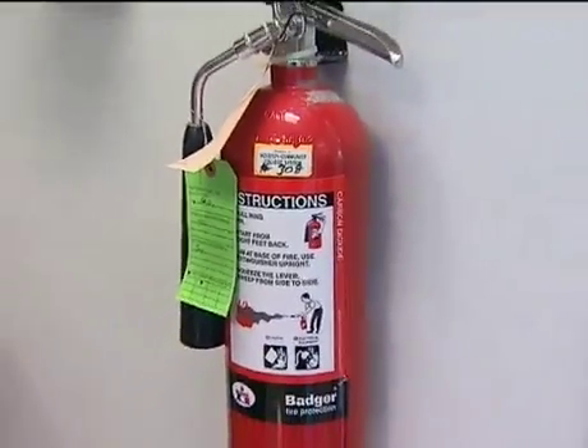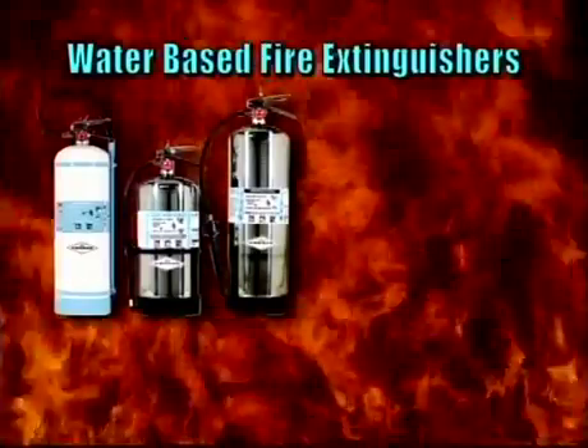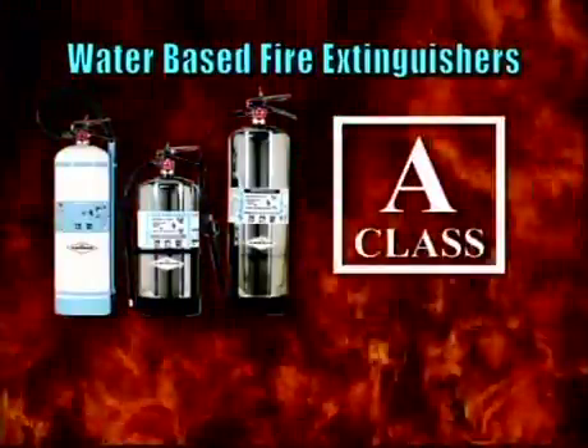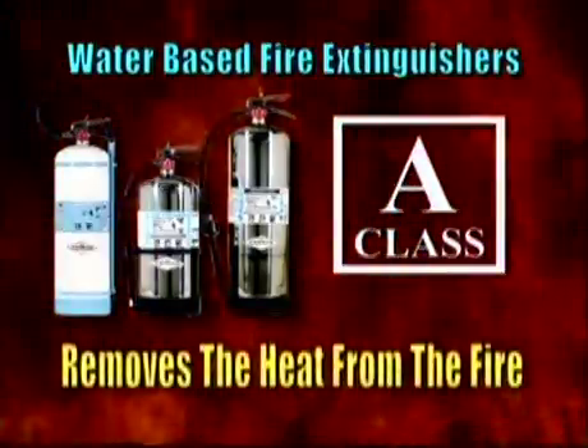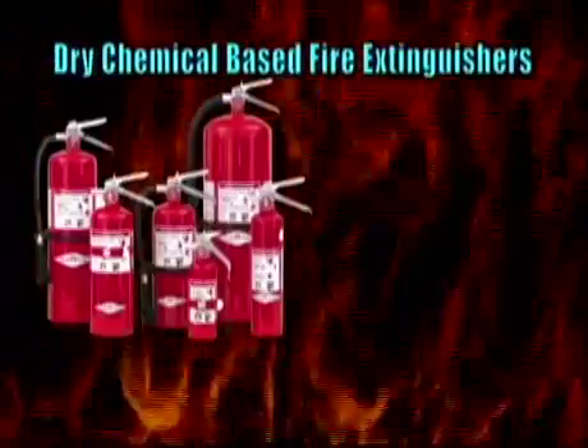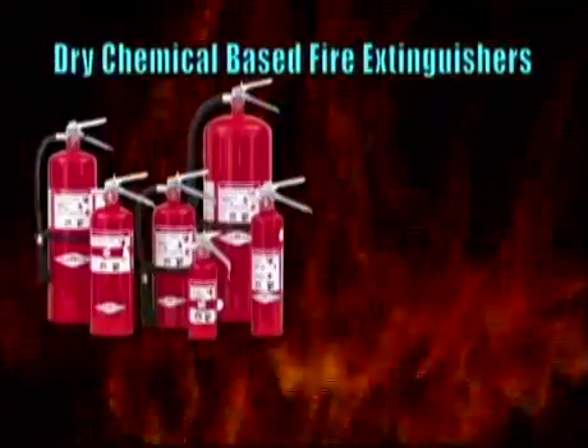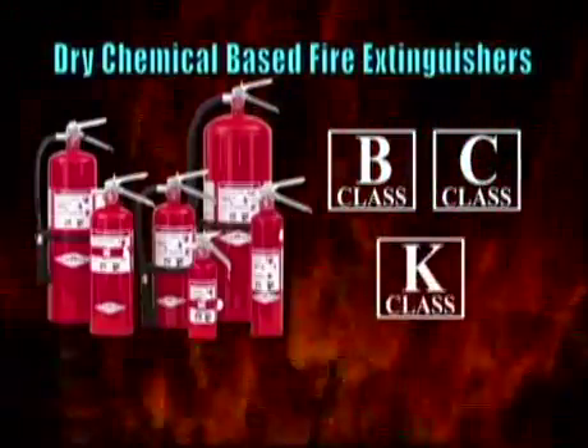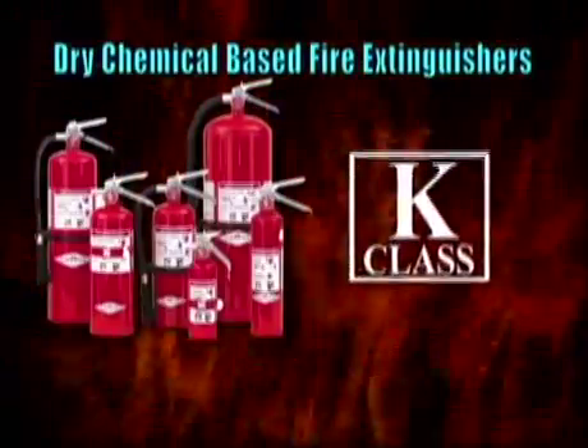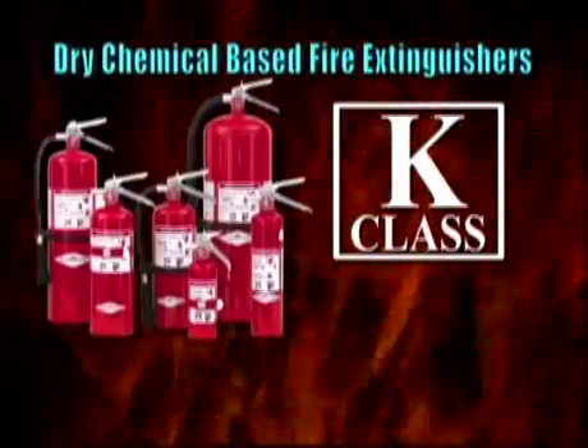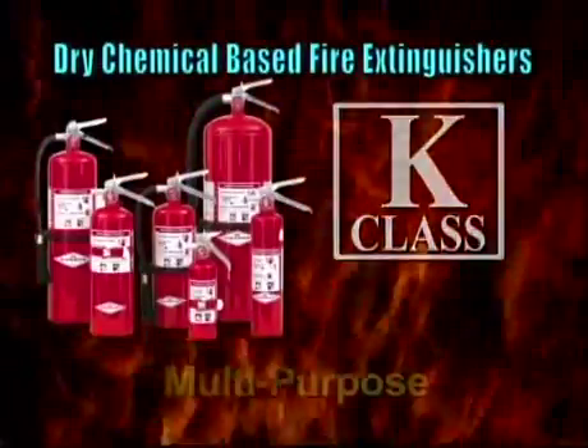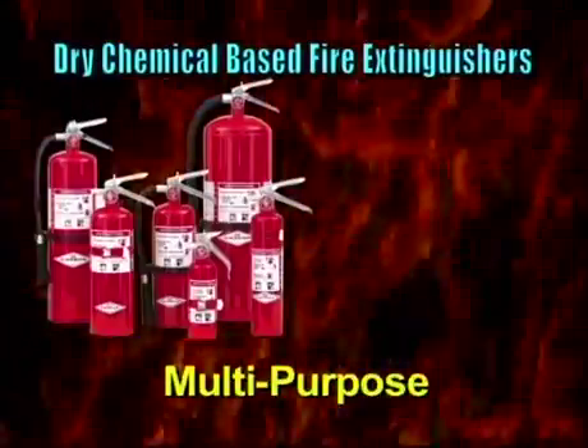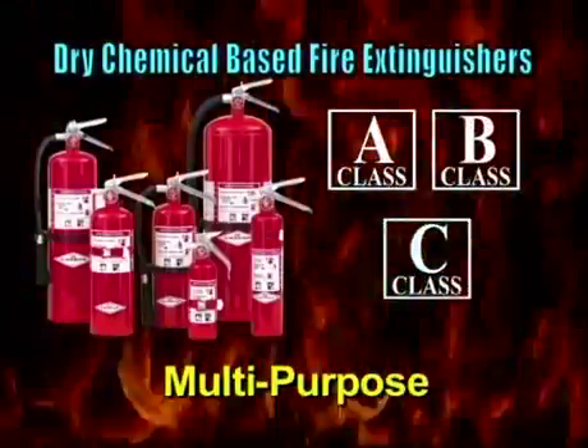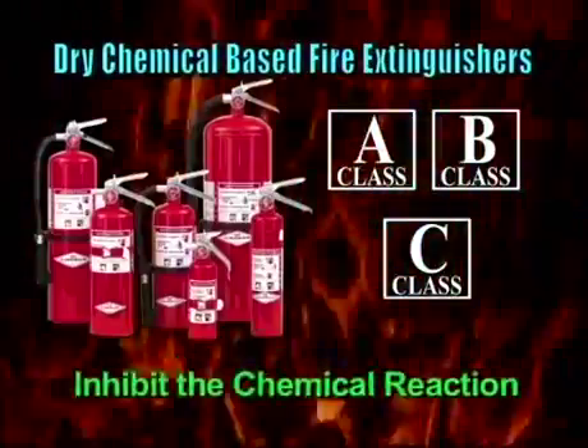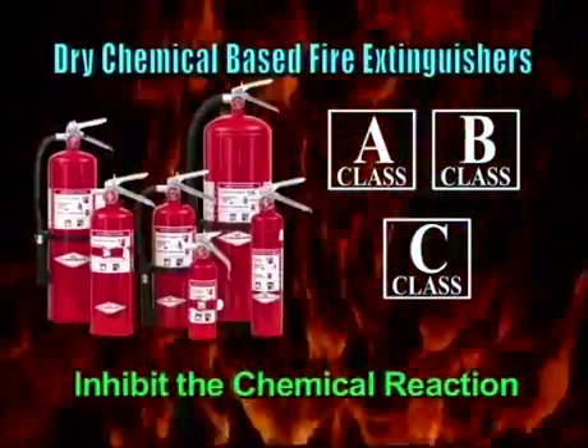It is important to know what type of fire extinguisher to use on the proper class of fire. Water-based fire extinguishers are to be used on Class A fires only. This removes the heat of the fire. A regular dry chemical-based extinguisher can be used on Class B, C, and K fires. They are not used as much for Class K fires anymore, with the advent of wet chemical extinguishers. A multi-purpose dry chemical extinguisher is effective on Class A, B, and C fires. Dry chemical extinguishers inhibit the chemical reaction of a fire.